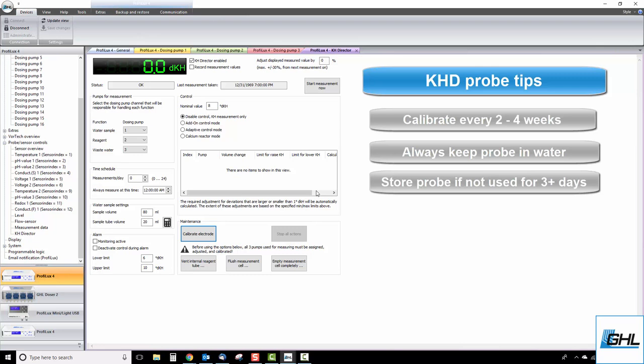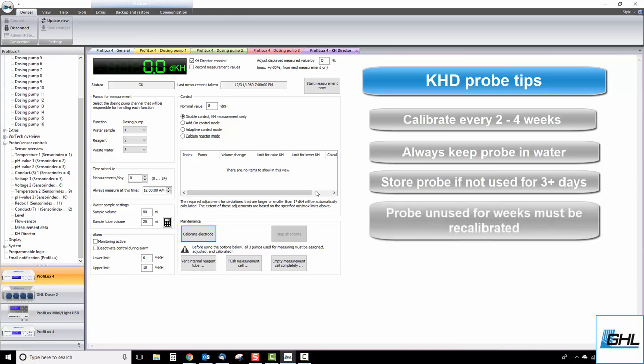Naturally, the KHD will always store a small amount of water inside the measuring cell to prevent the probe from drying out. With each test, this fluid is flushed out and replaced with new water. Lastly, a probe that has not been in use for more than a few weeks should always be recalibrated before being put to use.